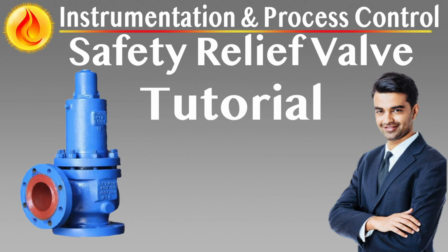Additional requirements for specific services. Oxygen and high-pressure air service. Relief valves intended for gaseous oxygen or air service above 50 barg must meet additional cleanliness, safety, and design requirements. Key provisions include special cleaning procedures to remove oil, grease, and hydrocarbons, use of non-reactive materials in flow path and sealing elements, packaging and shipping with strict contamination controls, clearly marked identifications such as "suitable for oxygen service."